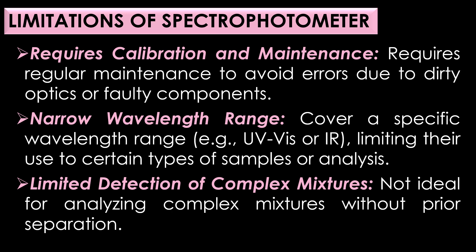The third limitation is requires calibration and maintenance — accurate results depend on frequent calibration with standard solutions, and the spectrophotometer also requires regular maintenance to avoid errors due to dirty optics or faulty components. The fourth limitation is narrow wavelength range — most spectrophotometers cover a specific wavelength range, limiting their use to certain types of samples or analysis.